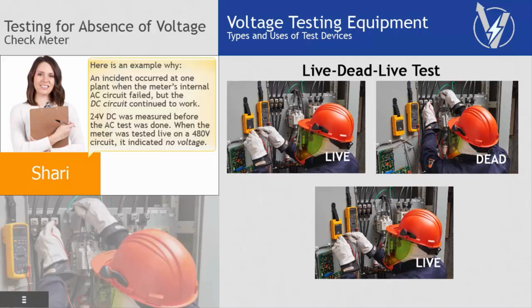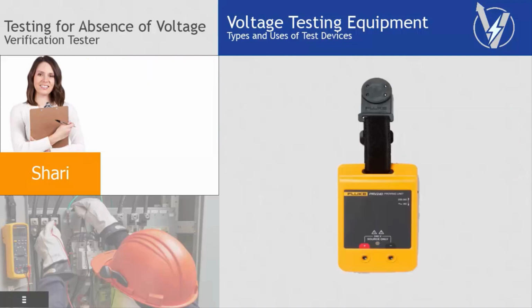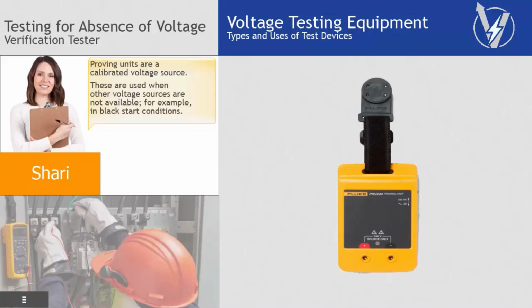Here's an example why. An incident occurred at one plant when the meter's internal AC circuit failed, but the DC circuit continued to work. 24 volts DC was measured before the AC test was done. When the meter was tested live on a 480-volt circuit, it indicated no voltage. Proving units are a calibrated voltage source. These are used when other voltage sources are not available, for example, in black start conditions.